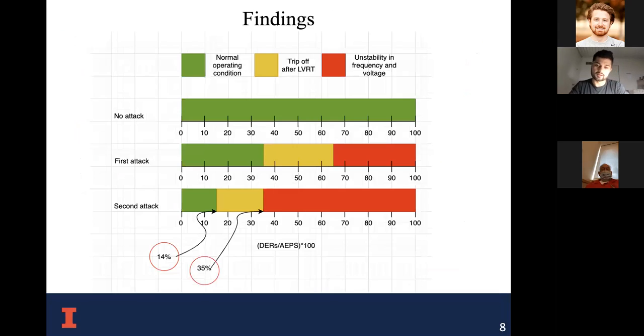So that's why it's important to consider tripping right off versus riding through separately, and we can see this on the last figure. I think the last figure summarizes everything because it shows the first attack and second attack going through. If your DER size is less than 14%, you're fine. Even if you do a mode change, like we said, from 0.44 PU injection to negative 0.44 PU, it doesn't really matter if your DER size is less than 14%. But if your DER size is between 14 and 35%, it's going to ride through and then trip off. And after 35%, it just collapses and trips off immediately.